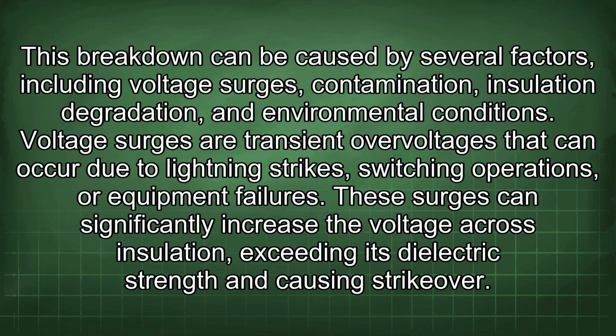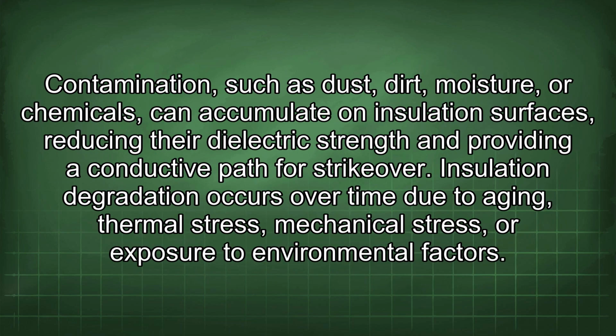Voltage surges are transient overvoltages that can occur due to lightning strikes, switching operations, or equipment failures. These surges can significantly increase the voltage across insulation, exceeding its dielectric strength and causing strikeover.